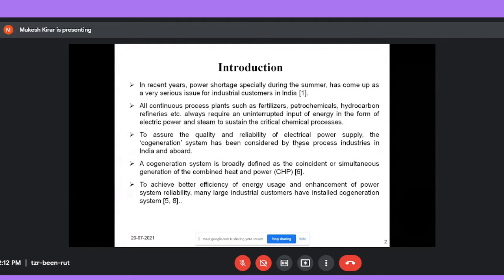A cogeneration system is broadly defined as the coincident or simultaneous generation of combined heat and power. Heat means the steam for the process, and power means electrical power, to achieve better efficiency of energy use and enhance power system reliability. When industry generates its own power for the load, the reliability of its supply improves, and it will not depend totally on the grid for its electrical power requirement. It can fulfill that requirement by its own generation.